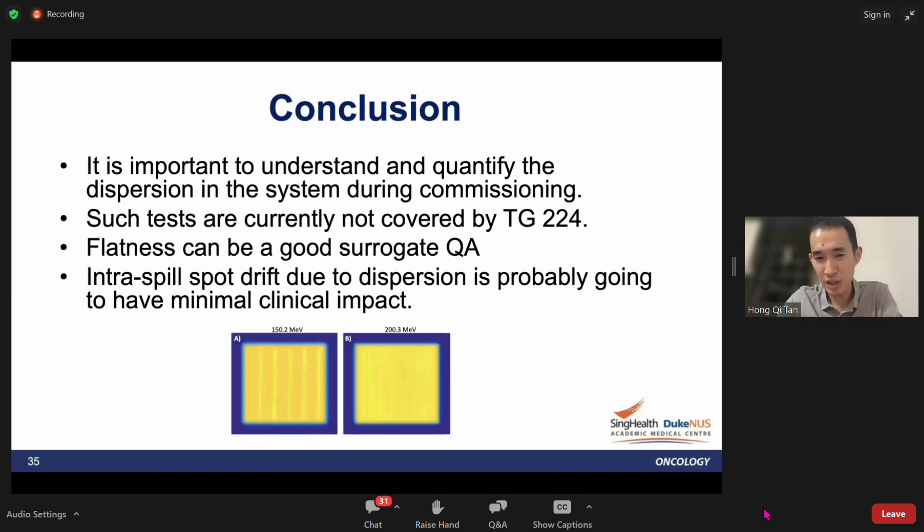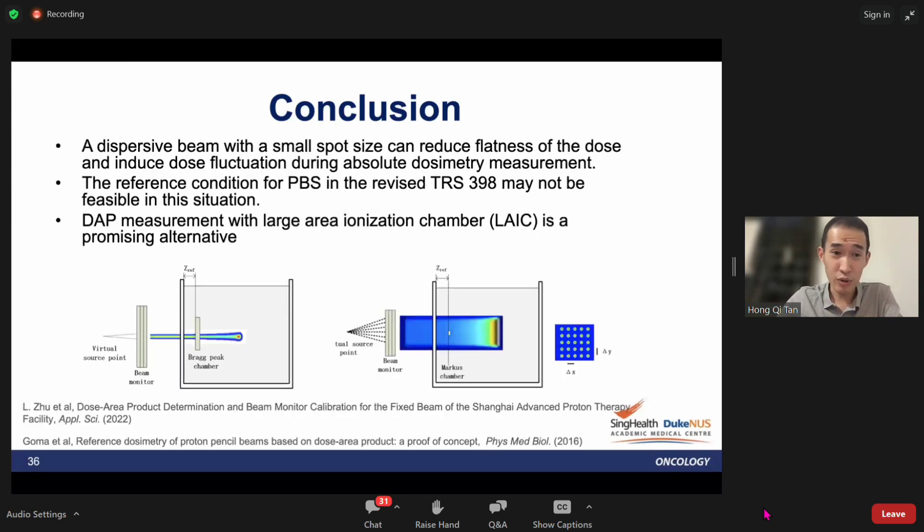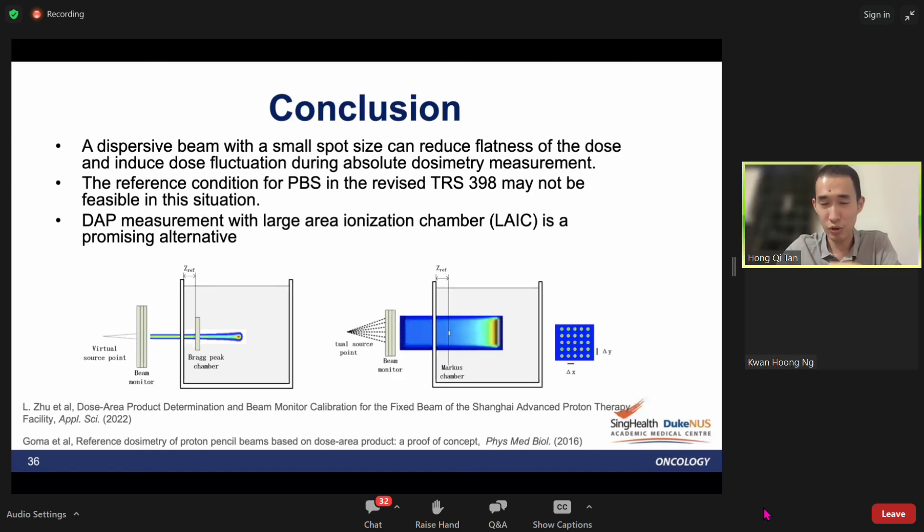The last point is the intra-spill spot drift chances are it has minimal clinical impact because during realistic clinical treatments at SOBP, the spot reaches about 4-5 mm sigma in water. With this spot width, if you have 0.5 mm spot drift, it doesn't change the dose distribution much. Nonetheless, the main problem is that dispersive beams induce dose fluctuations in your absolute or reference dosimetry measurement. You could introduce wrong input data into the TPS, which will have far-reaching consequences to the patients. That's why it's important to do this once during commissioning.